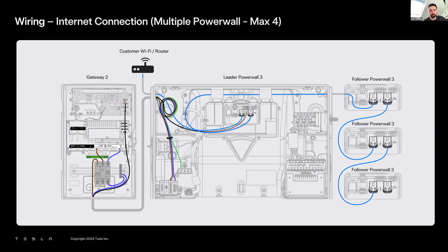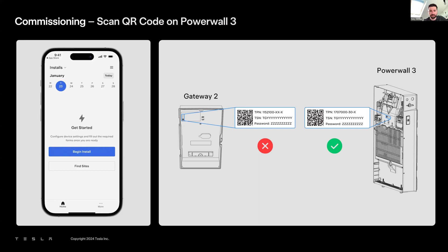From a commissioning perspective, you scan it at Powerwall level now. You do not scan the QR code in the gateway anymore. Once wired up, you scan the QR code, and in the Tesla One app it will start the commissioning process, taking you step by step through everything needed to ensure the system's up and running. You'll see red crosses and green ticks as you go. All green ticks means the site's good to go and you can pack up. A red cross means something's not been done or there's an issue, and our support team is there to support you.